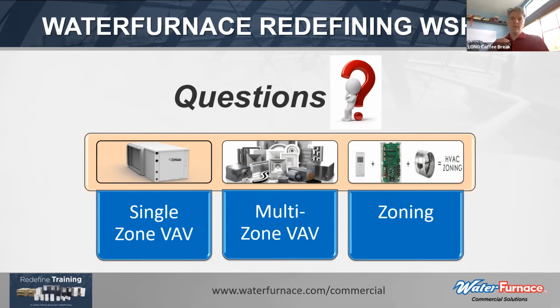So other than savings from the initial cost of the units, the installation of the units, even the handling of the units to the specific job site, having that diversity is going to make your job as an engineer a lot easier, because undersizing is certainly a problem, but oversizing can be just as difficult a problem to try and solve once it's in the field. So this eliminates a lot of that risk. Zoning is very important, but it's extremely flexible with this. If you have a very specific zone, let's say a conference room that you don't want to overheat or undercool, you can certainly add an additional unit just for that, but still take benefit of all the surrounding spaces for this variable type. So this gives you a lot of flexibility.